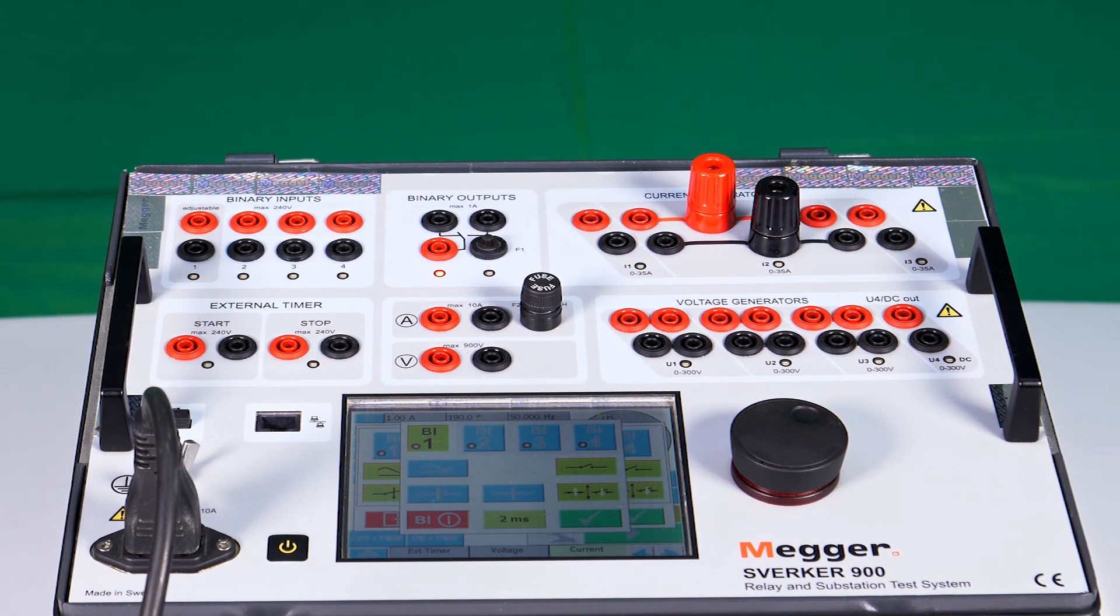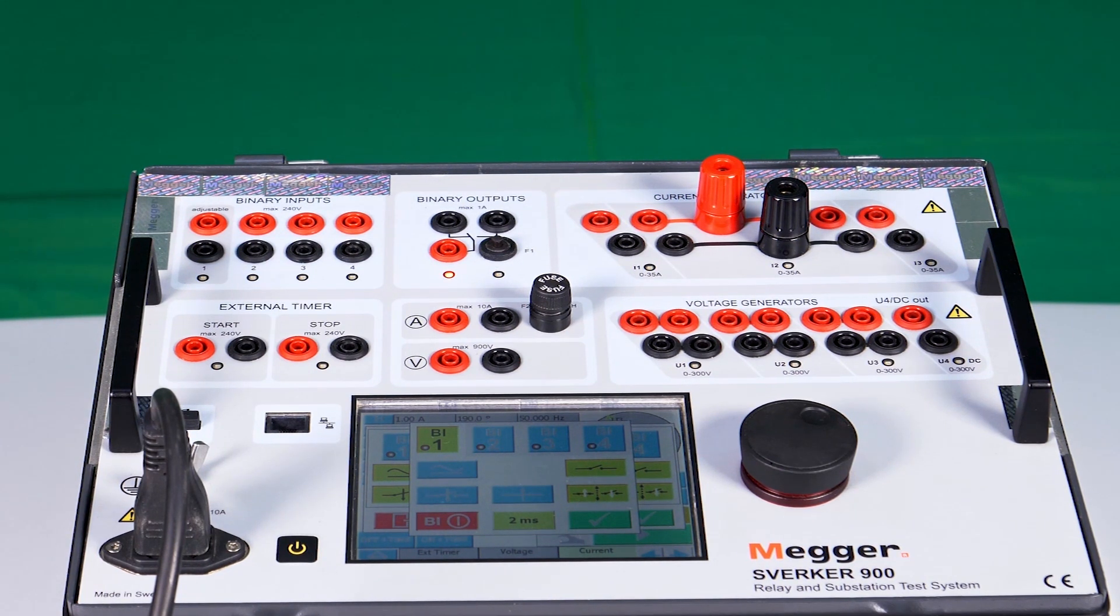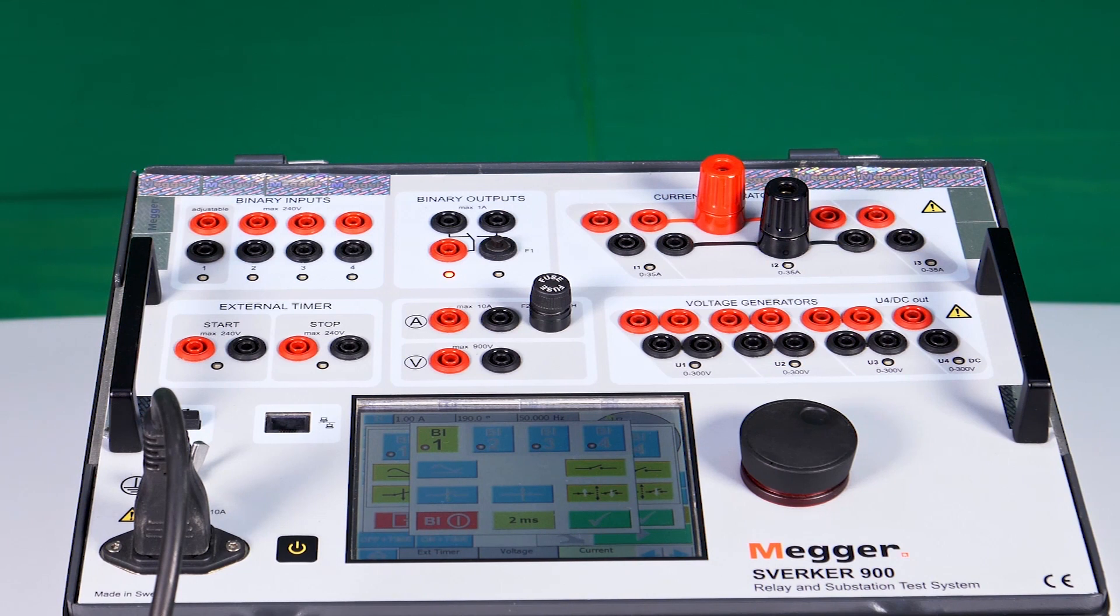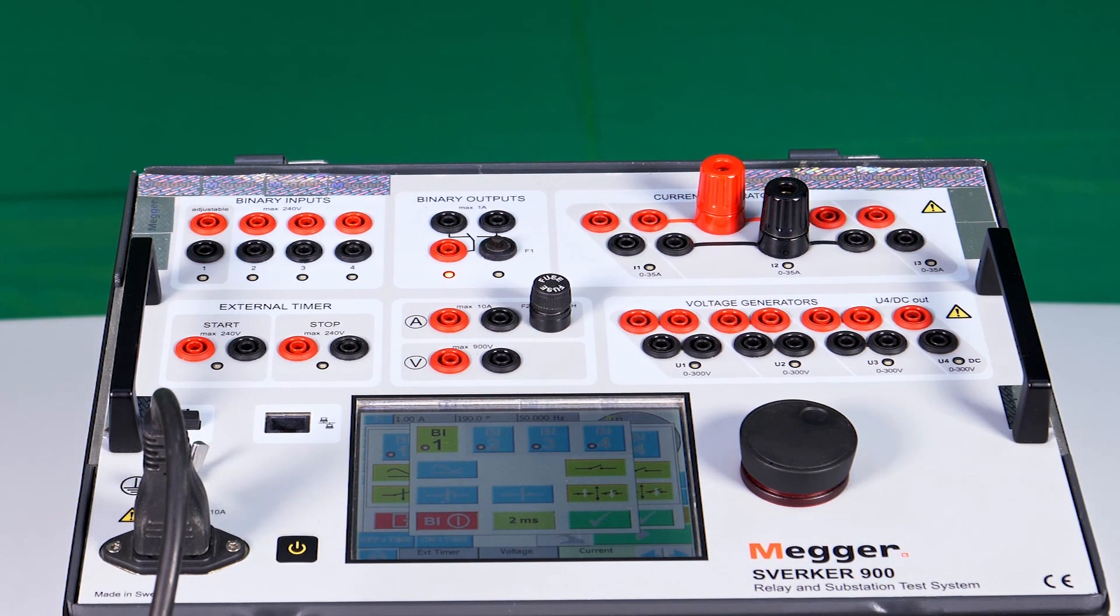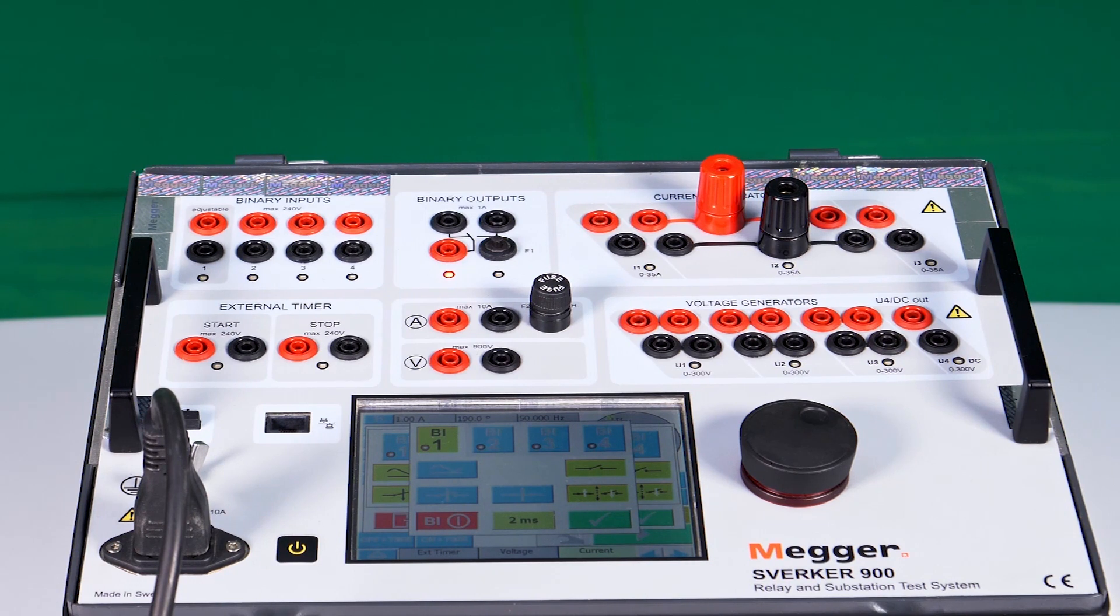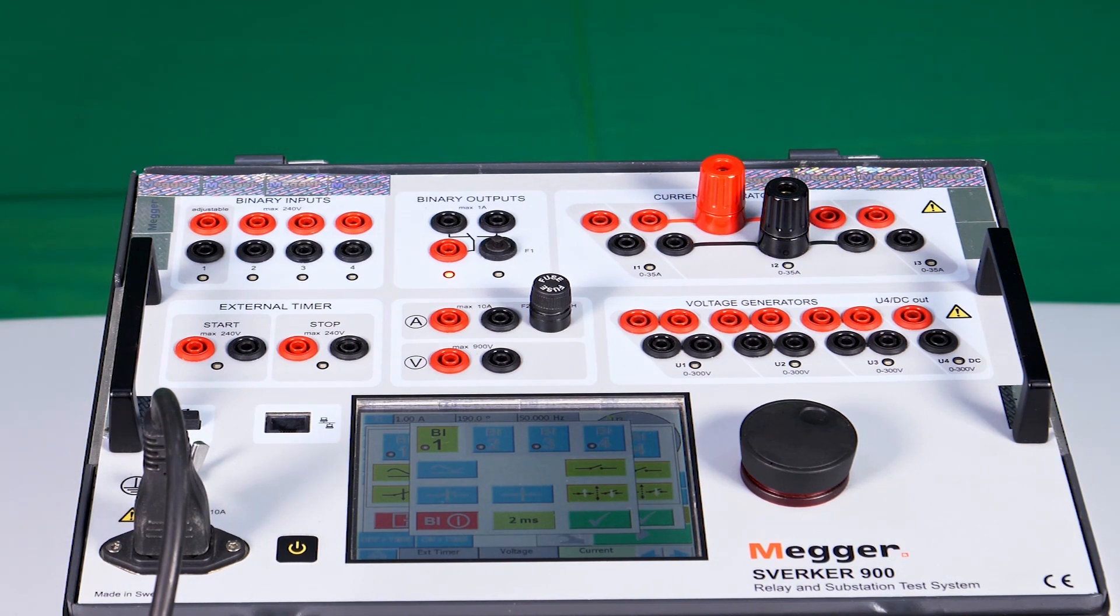The term change of state means the initial position of BI will be considered as a reference position. When the state change is detected, the test kit will detect it as successful relay operation. The initial position can be NC or NO.